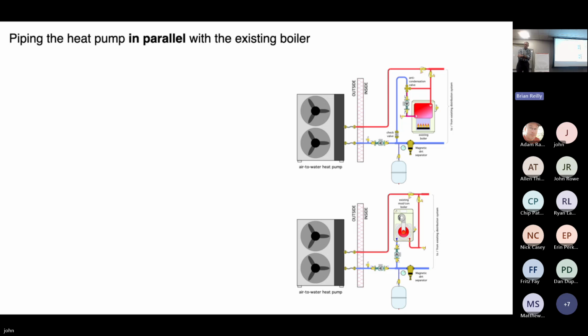I'd be intrigued if, since we're asking people to explore this, we could show a cost savings to condition their home with this system, which could also provide cooling. I think that would certainly help to sell. Yeah, and to find that economic balance point, you would need to know the COP of the heat pump as a function of outdoor temperature. And the capacity as well, and what the competing fuel prices are. Then you could make a calculation. What's the lowest cost per million BTUs? Is it the heat pump? Is it the boiler? And then determine when that switchover is going to occur. That's not necessarily a fixed temperature. It could vary depending on the performance of the heat pump. As your air temperature goes down, your COP is going down. But that could be done.